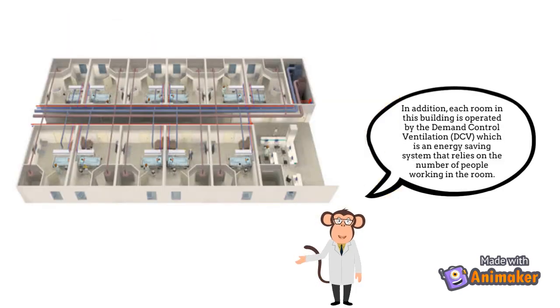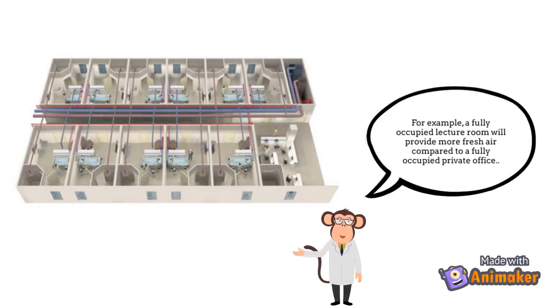Each room in this building is operated by demand control ventilation, an energy-saving system that relies on the number of people working in the room. For example, a fully occupied lecture room will provide more fresh air compared to a fully occupied private office.